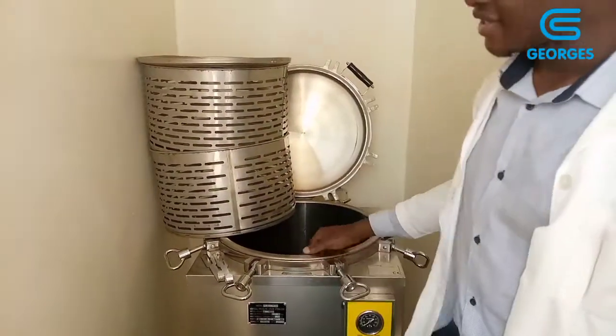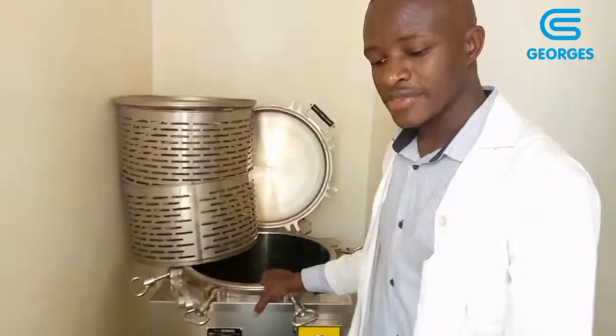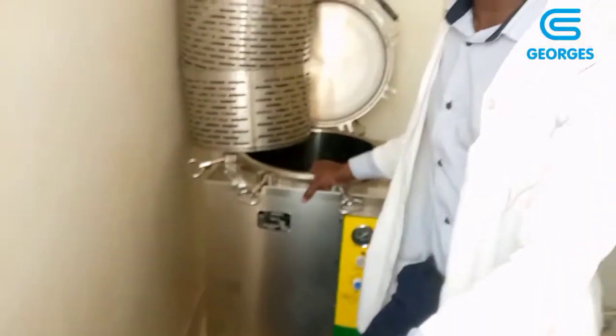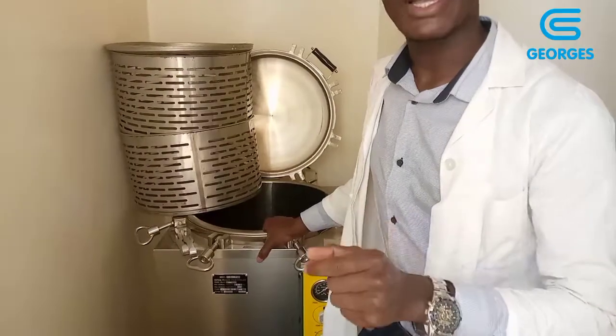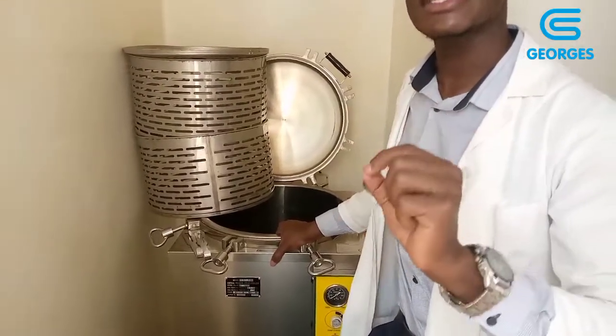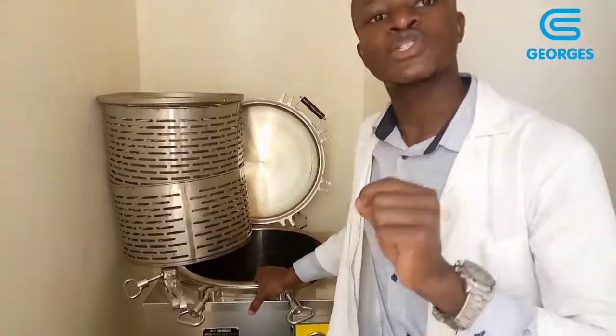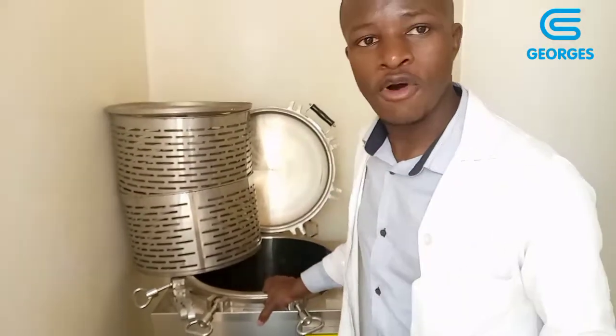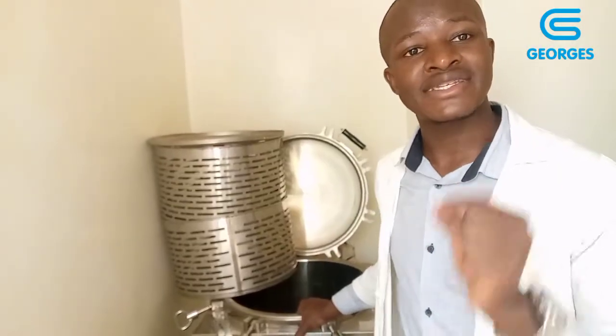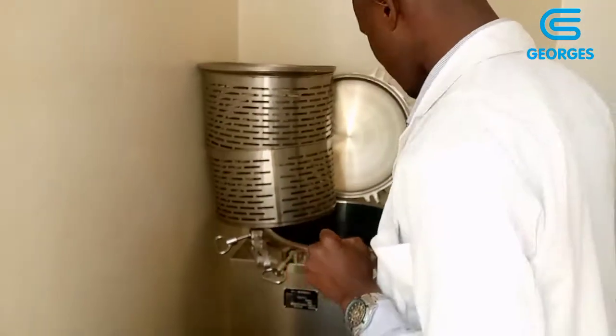The machine that you're seeing here is called an autoclave, and the autoclave operates under the principle of high temperature and pressure. The high temperature and the high pressure is what kills the pathogens and includes the spore forms. Spore forming organisms like Bacillus anthracis are not able to survive when you put them in the autoclave. So let me show you how the process is done.